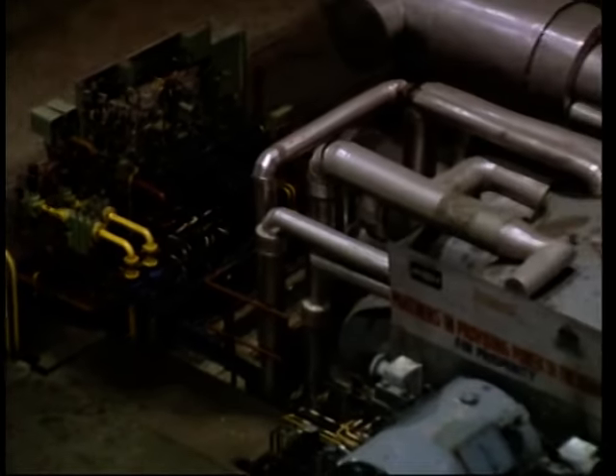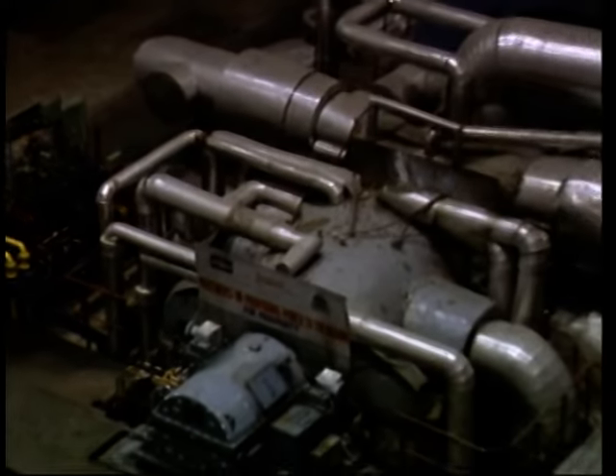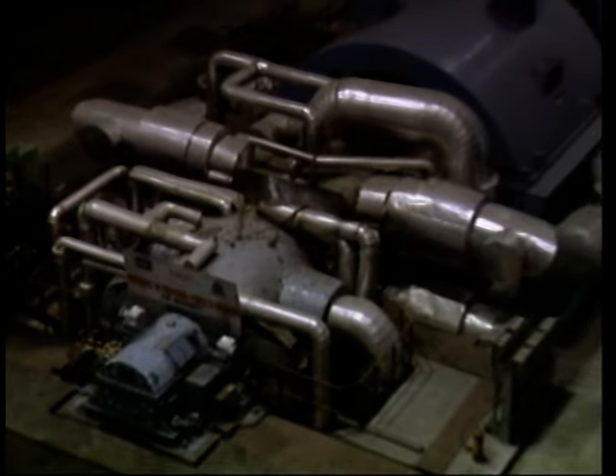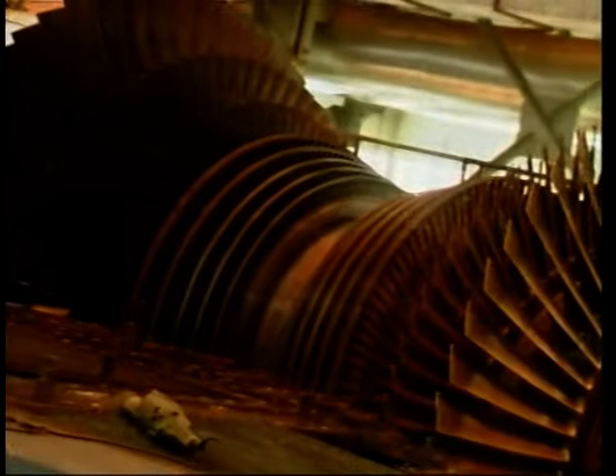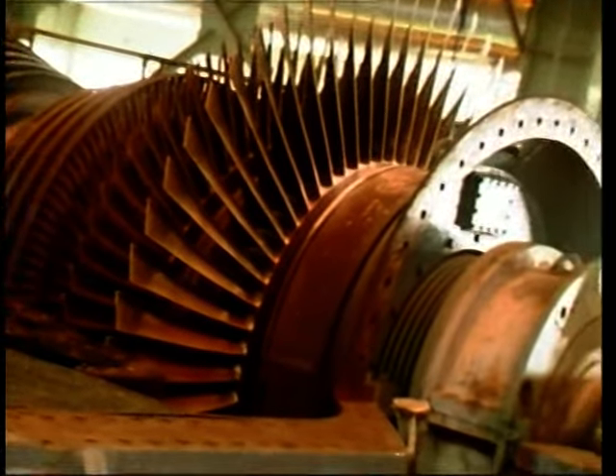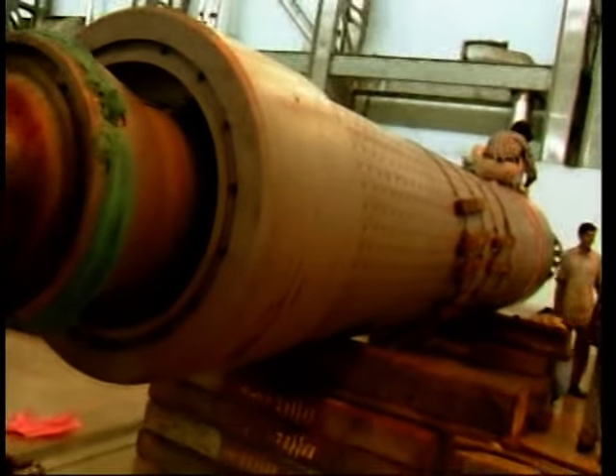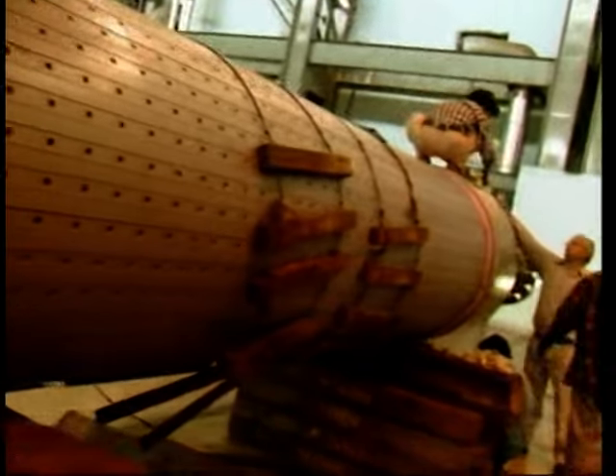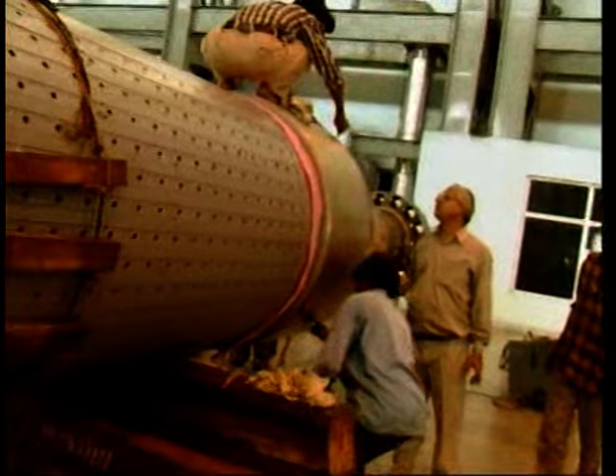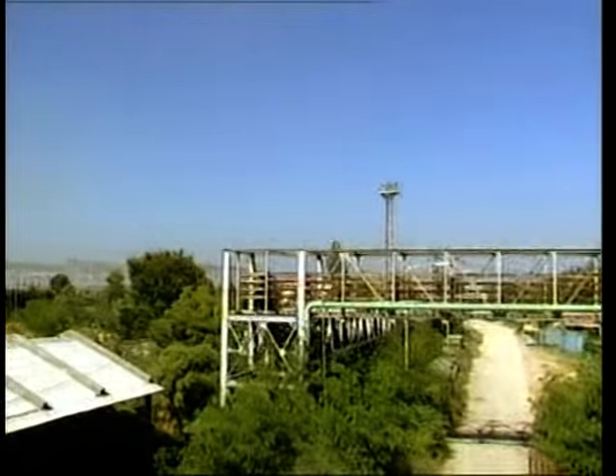A pipe then feeds the high-pressure steam generated in the boiler to a turbo generator. A turbo generator uses the kinetic or reactionary energy from the steam to spin the shaft. This shaft is connected to an electrical generator and produces electricity as it turns. The turbo generator runs at a speed of 3,600 revolutions per minute and generates 210 megawatts of power.